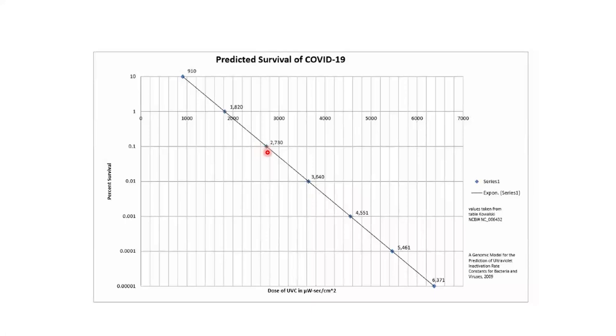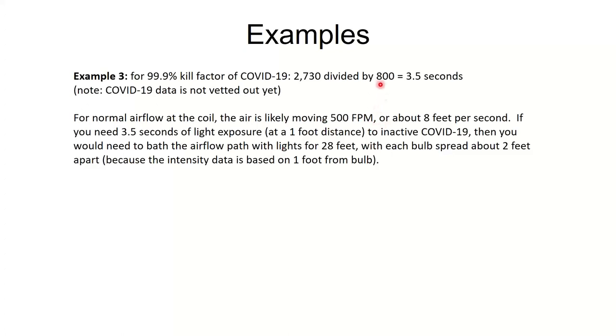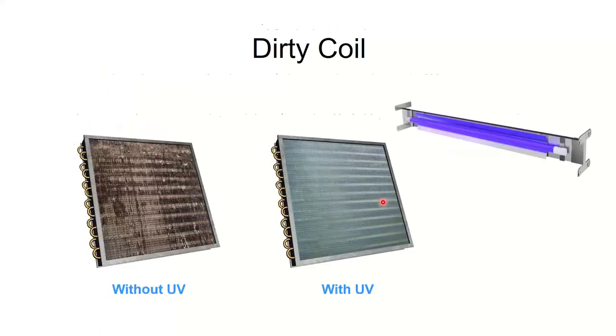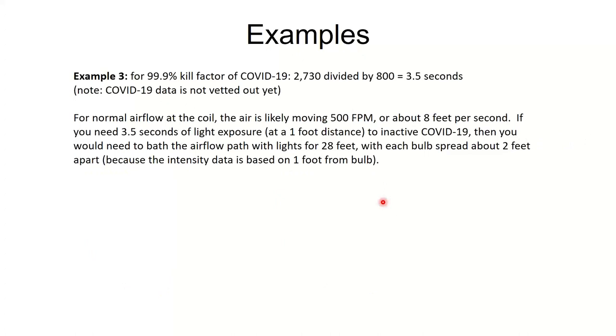So if I want to get to 99.9% of the elimination of these, meaning only 0.1% survive, I need 2730 as my dosage. If I throw that into my previous formula with my 800 bulb, that comes out to 3.5 seconds. So I'm still going to need a pretty good amount of distance of lights bathing that airstream in order for me to get 3.5 seconds of shine time moving at 500 feet per minute or 8 feet per second. It's pretty fast. So I'm going to need a lot of distance and a lot of bulbs to do that. So what does all that mean? It means you're probably not going to kill COVID with a UV light.